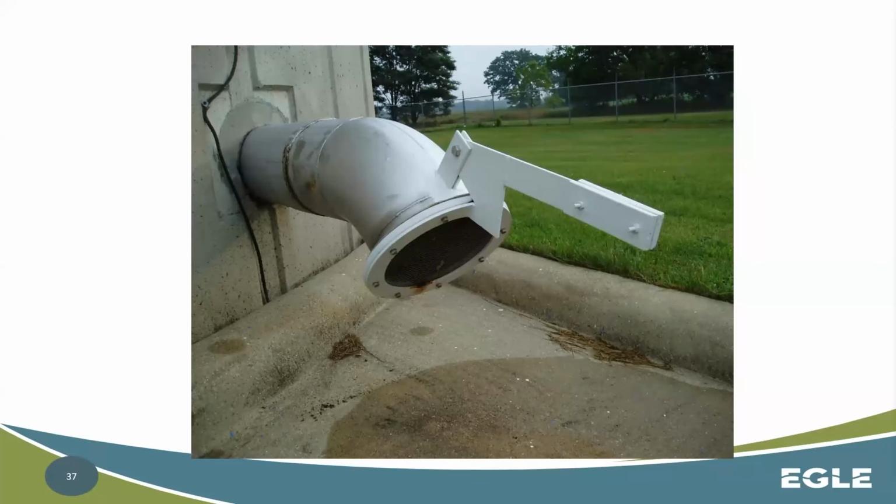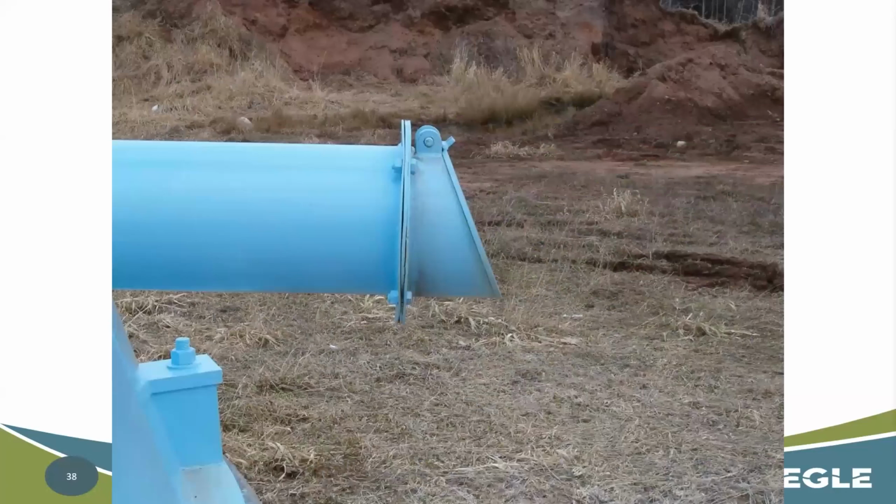Now you're not having any storage, things like that. Okay. So we would ideally like a full metal flap. You can't see it super well here, but you're going to have to take my word for it. This is a full metal flap here, so you're not having that same chimney effect, which is good.